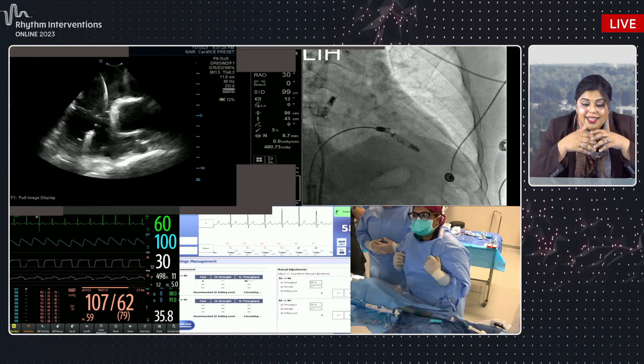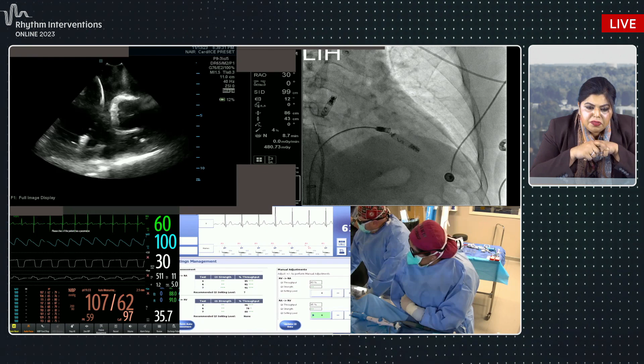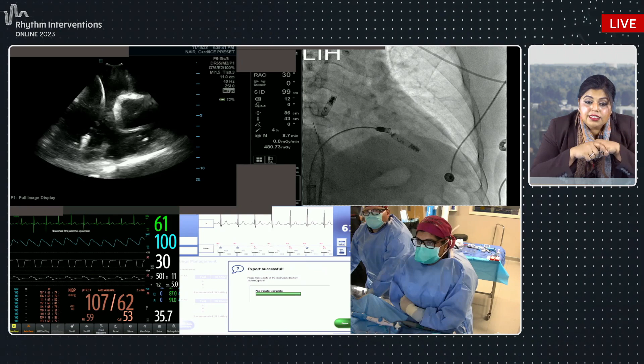But you're pairing the device, but you're also selecting or testing the i2i strength. And you can see on the programmer that we are looking at the i2i strength and the throughput between the two devices. It does automated testing. It starts at 4, sees what the throughput and i2i are, and you can see I have 2 stars on the i2i and about 95% on the throughput, and it goes up to 6 and 7, checks it, and after it does the analysis, it recommends what the programming needs to be for the throughput and for the strength.